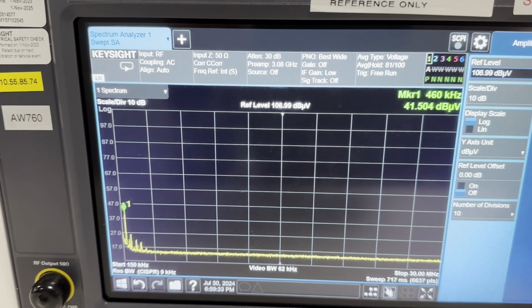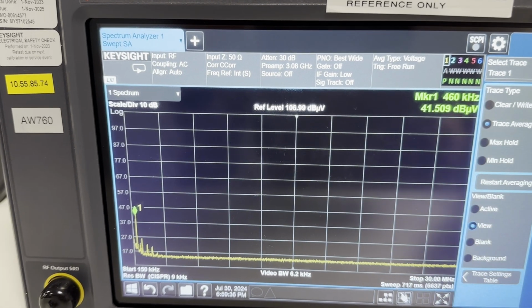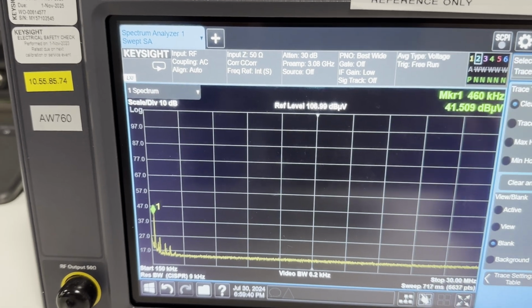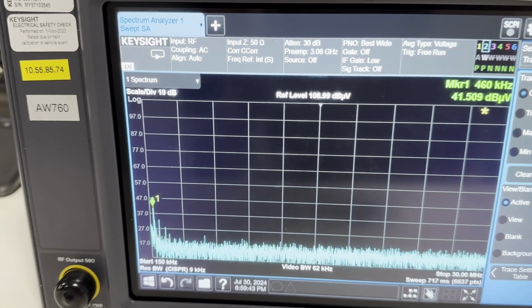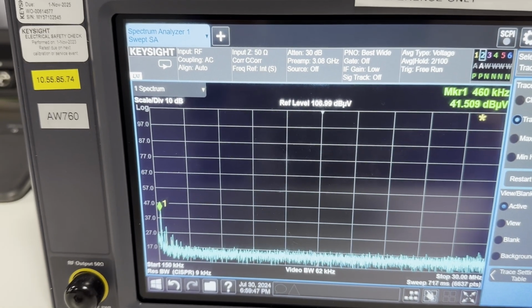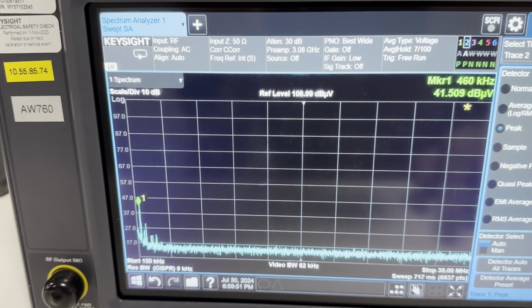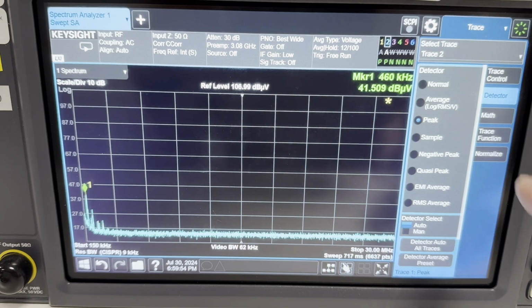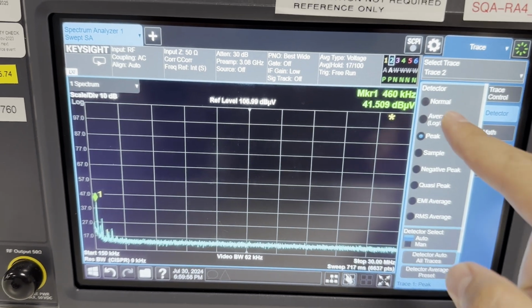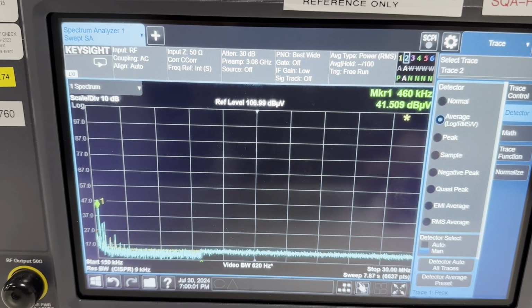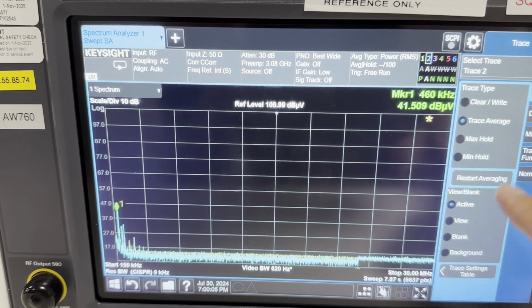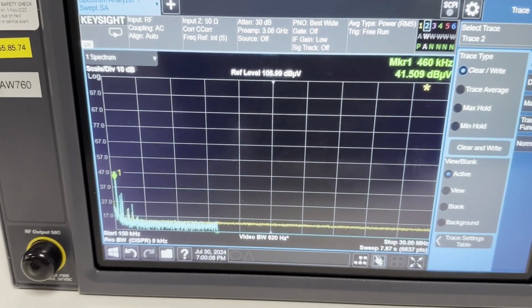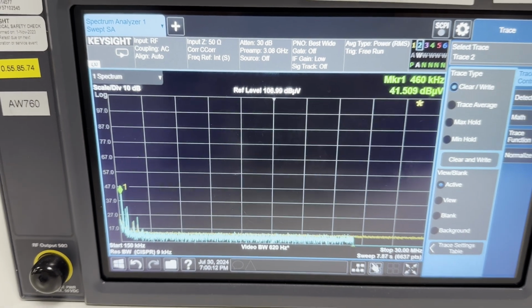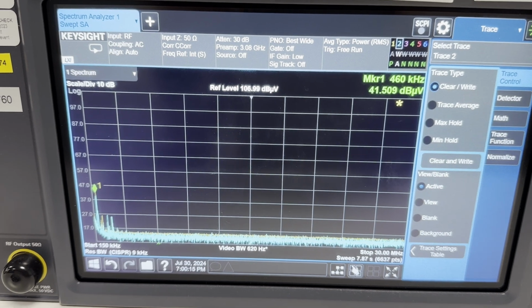Alright, so this is effectively the capture, so we can capture that noise floor, and yeah, I always average it. Oh yes, and detector, in this case I was using peak, but I think for the best results of conducted emissions you should be really using the average detector. So now it's actually taking an average of an average, which is not really any point, so it's already taking the average when you're using the average detector. So that's good enough, and now we can go without powering the DUT.